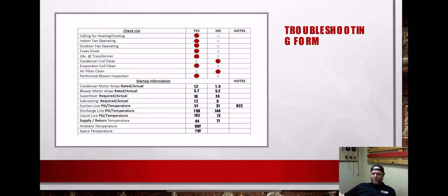and asking for some help. Condenser fan motor amps, what's your rated, what's your actual? Your blower motor amps, what's your rated, what's your actual? Superheat required and actual, suction line temp, or your suction line pressure and your suction line temp, your discharge line pressure, discharge line temp, same thing with the liquid line. And finally your split, which is your supply and return.